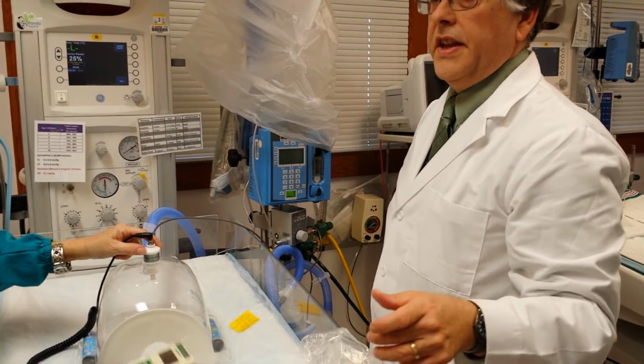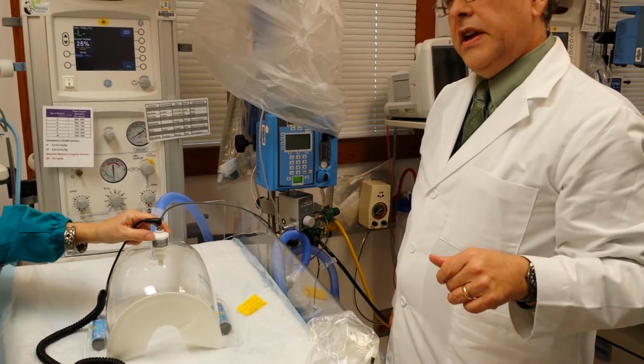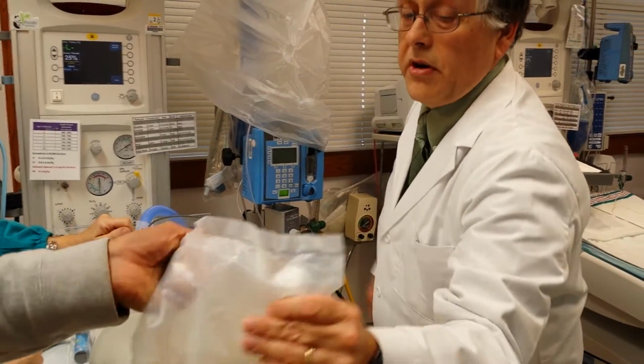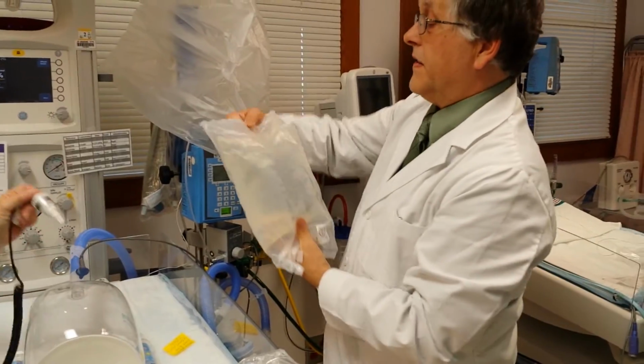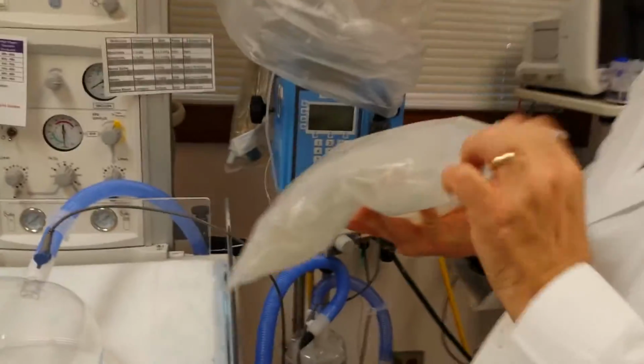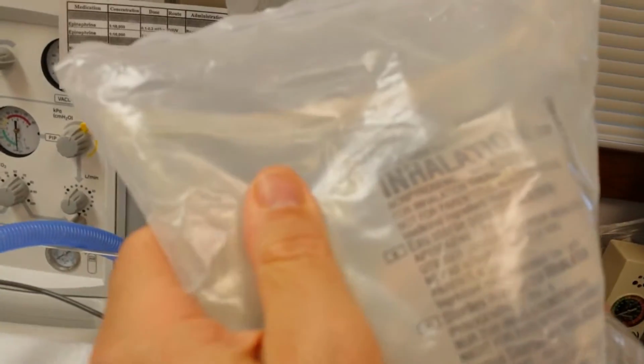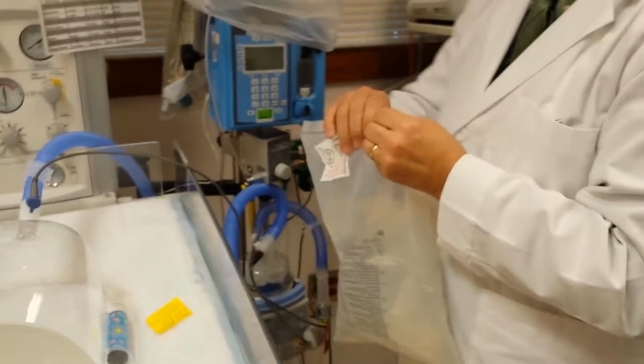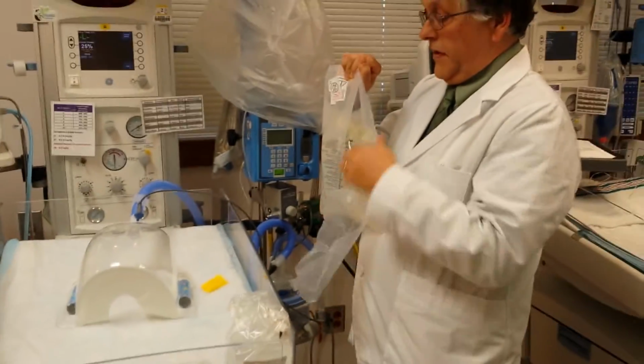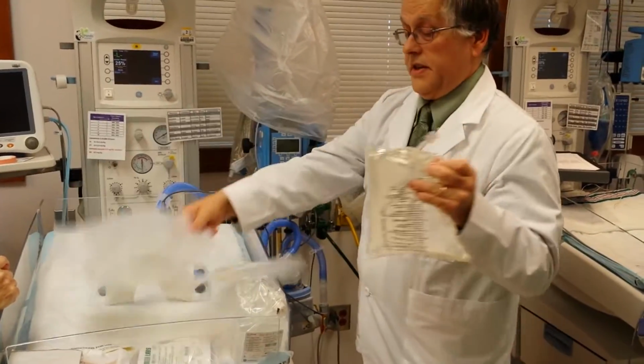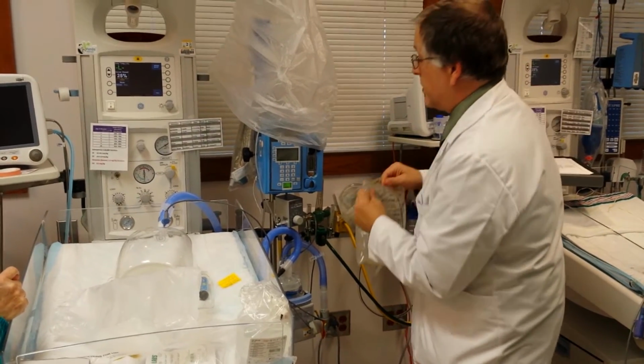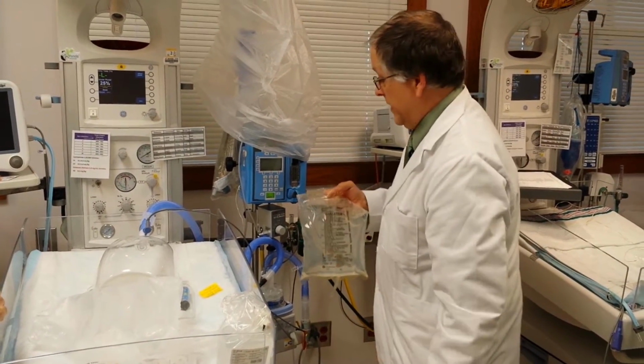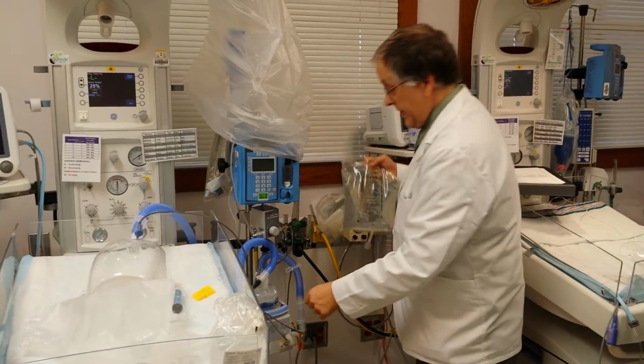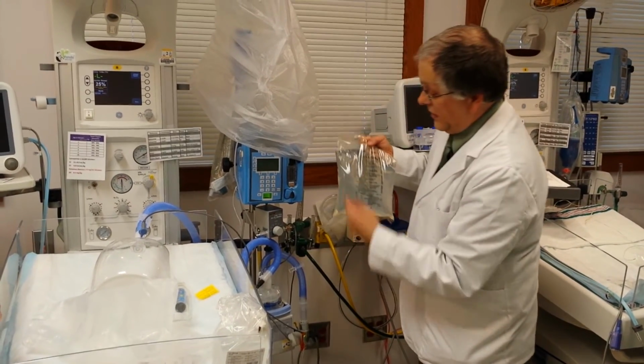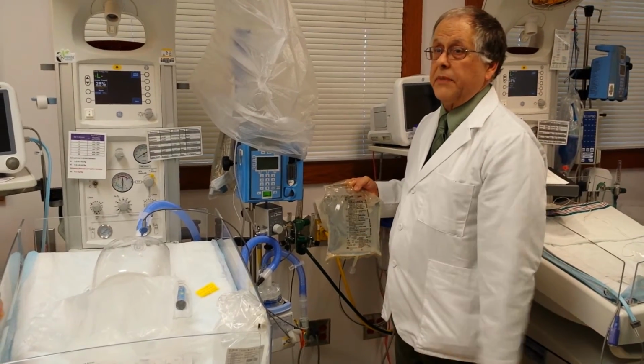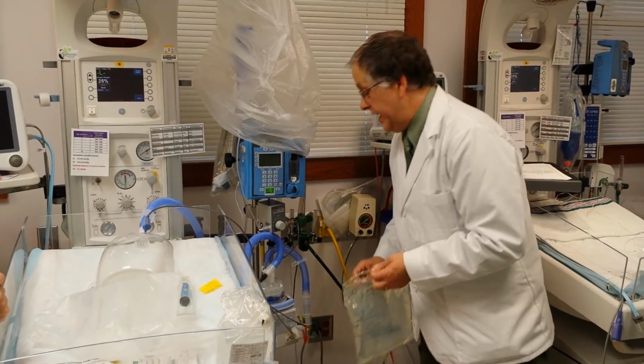I'm sure it's inhalation water, and it either comes in this big bag or a smaller bag. Let me confirm. Yeah, sure enough, it says inhalation water. Okay. Inhalation. That's for the oxyhood or for the ventilator. It's the same water we use for a ventilator. Okay. Then you hang this. I'm not going to pierce it now to conserve it. Then I'd have to throw everything away. But then you just pierce it here, in there, and then it'll automatically autofill, maintain the proper level. And then the last thing is turn the heater on.